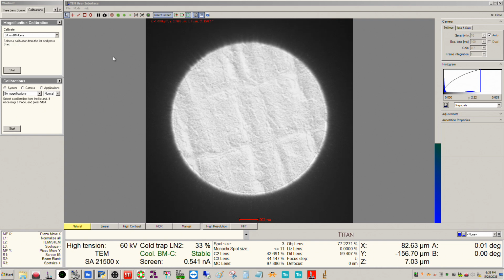So we just did the alignment for Microprobe STEM, and you definitely need to do that before you do this calibration, but you also need to have STEM mode properly tuned up as well, okay? So you need to have done your corrector tuning and that be in good shape as well, because that actually is the initial start when you do the mag cal in Microprobe. I know that seems kind of counterintuitive, but it's actually the case, okay?